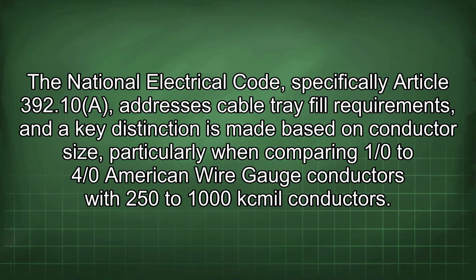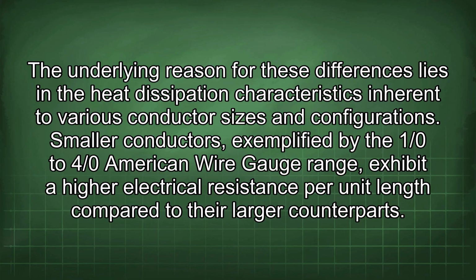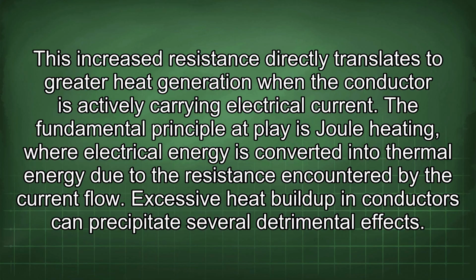The National Electrical Code, specifically Article 392.10(A), addresses cable tray fill requirements, and a key distinction is made based on conductor size, particularly when comparing 1/0 to 4/0 American wire gauge conductors with 250 to 1000 kcmil conductors. The underlying reason for these differences lies in the heat dissipation characteristics inherent to various conductor sizes and configurations. Smaller conductors, exemplified by the 1/0 to 4/0 AWG range, exhibit a higher electrical resistance per unit length compared to their larger counterparts. This increased resistance directly translates to greater heat generation when the conductor is actively carrying electrical current.